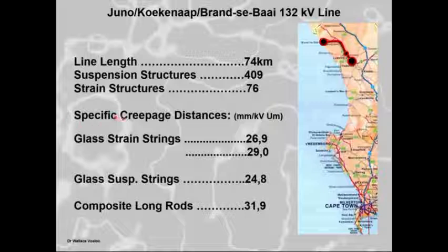Now, the specific creepage distances in millimeters per kV based on UMAX, so that was the old 815 technique of going for it. What happens is that there are glass strain strings running here, and they are at 26, 27, and 29 millimeters per kV. So they are insulated for very heavy, very close to very heavy, but heavy, on the upper side of heavy. Then on the suspension strings, we've got about 25 millimeters per kV, which is for heavy. So you can see that for the glass, this section here which is inland, we're running at about 25 millimeters per kV, and we're doing pretty well. So the glass is sitting here in this area.